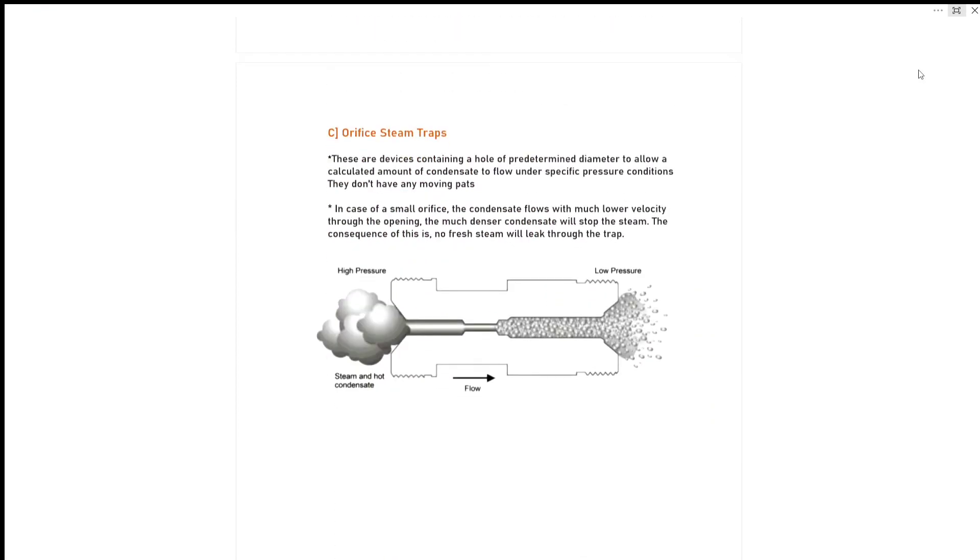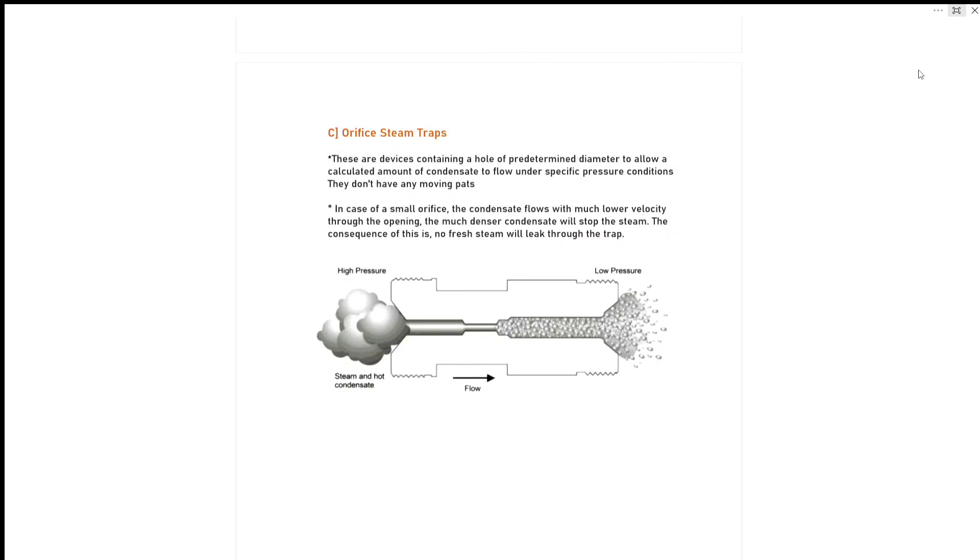Our third type in thermodynamic steam trap is orifice steam trap. These are devices containing a hole of predetermined diameter to allow a calculated amount of condensate to flow under specific pressure conditions. They don't have any moving parts. In case of a small orifice, the condensate flows with much lower velocity through the opening.